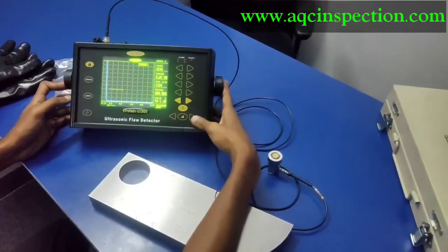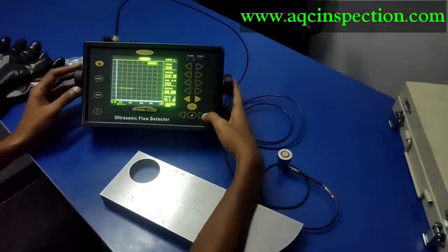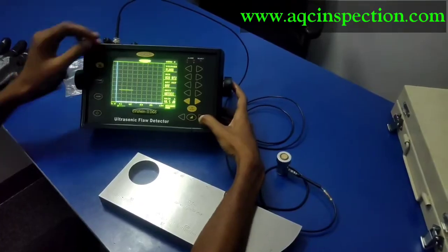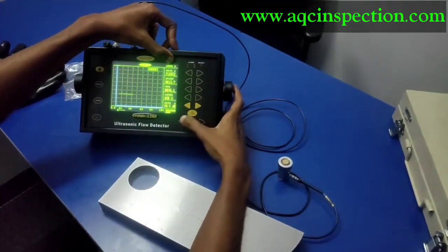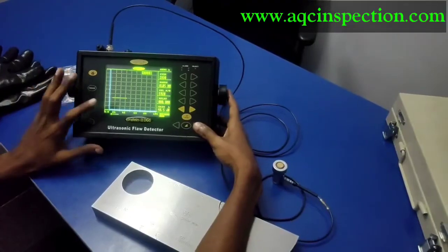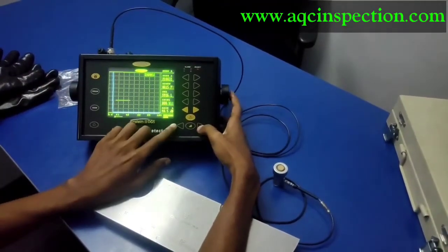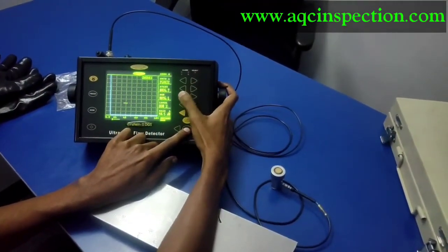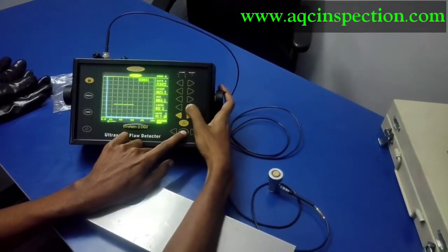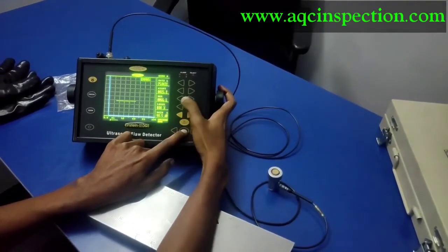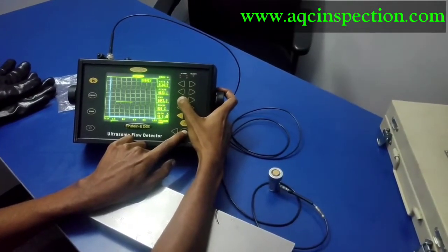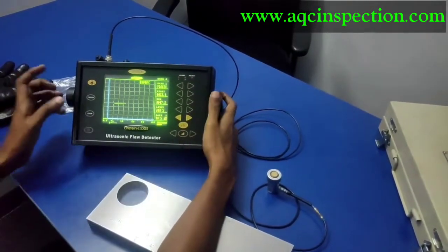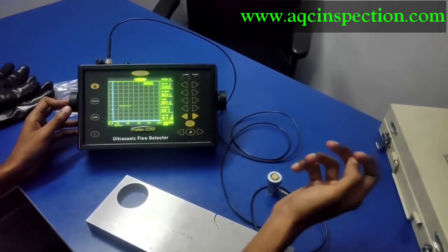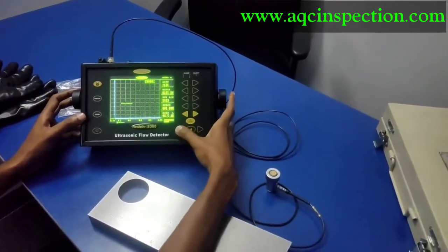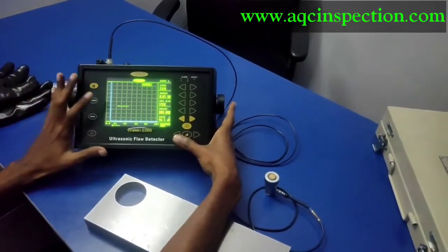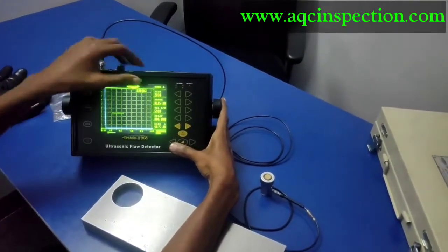As you can see, this is the ultrasonic flaw detector Einstein 2 DGS. We have a total of 11 menus. You can see here, menu 1, 2, 3 up to 11, and this green color line you see is called the gate. We can reduce, increase and decrease the gate also. This serves the purpose of detecting the size of indications or cracks or anything, or the dimension you can see by using this gate. We place this gate on the echo to see the signal here and here.